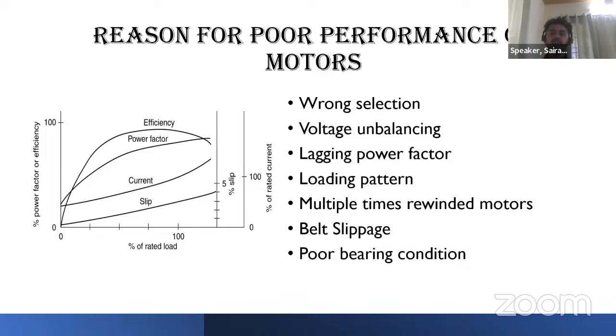And then multiple times rewinding the motors. If we keep on rewinding the motors, then the procedure that has been followed for winding the motor at the time of production won't be repeated during the rewinded condition. The efficiency of rewinded motors will be getting drastically reduced. If we keep on doing it for multiple times, then the original efficiency will be drastically reduced and the performance of motor won't be good. Then belt slippage is also a major reason. Poor bearing condition. If your bearing is not proper, then it will generate heat and there will be the jamming of rotor section. Then a huge amount of energy will be consumed for doing that work.